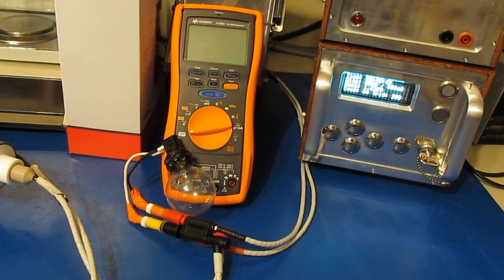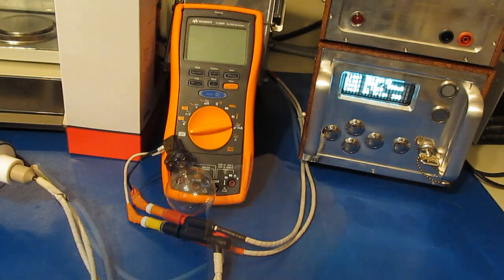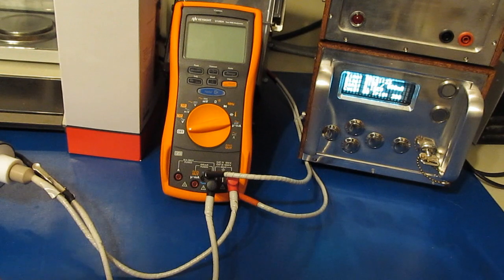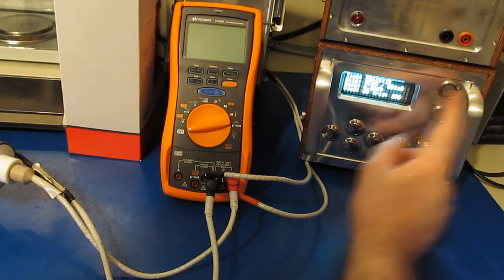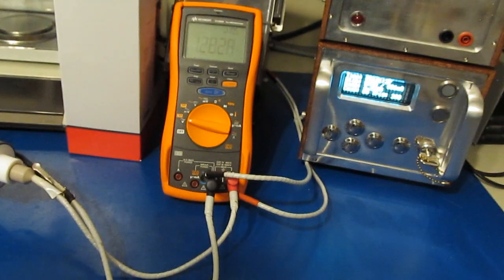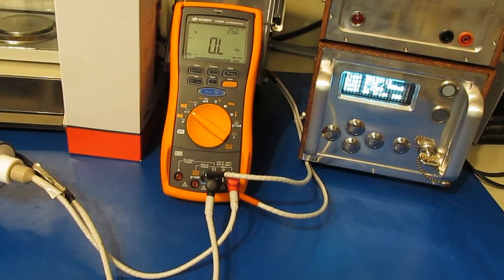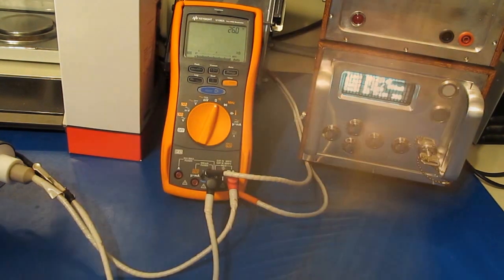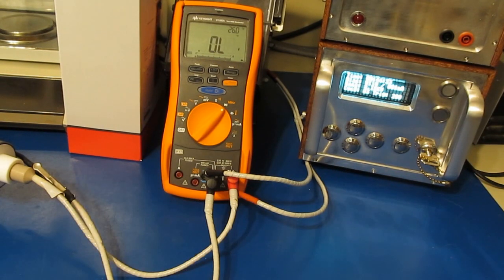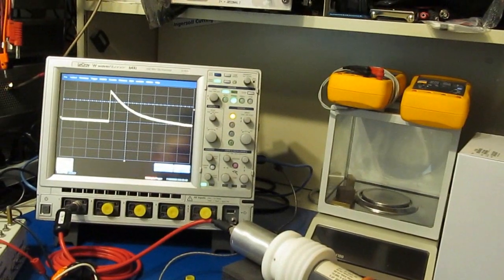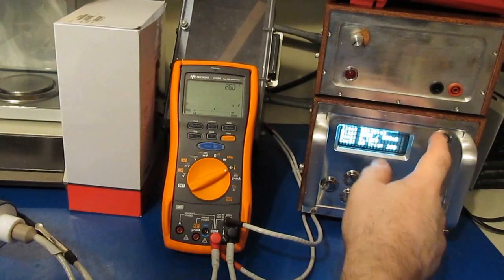Alright, you can see it's a little brighter. Again, this will be a 3,000 volt peak transient, 2 ohm source impedance, 100 microsecond full width half height. Again, 5 transients, both positive and negative, with the meter set to each mode. And that was the last transient that was applied to the meter. Again, no signs of anything breaking down.